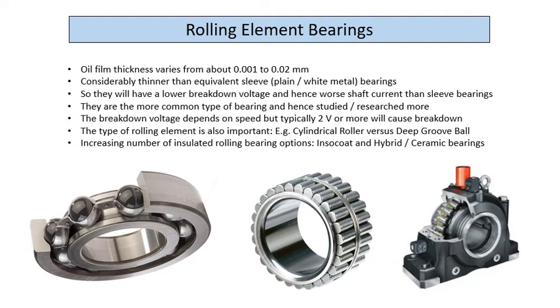And this is what I found, is that for rolling element bearings, your oil film thickness varies from about one 1,000th of a millimeter to 2 100ths. I can give you the reference of that. It's Prochard. And so this is considerably thinner than your equivalent sleeve bearing. So of course you'll have a lower breakdown voltage. Then I found another paper where the lowest breakdown that you get is around about 2 volts.